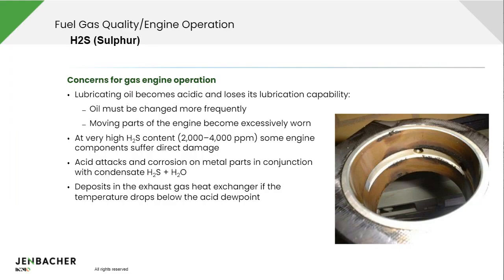The first topic is what Luis already alluded to: gas quality and gas treatment. The first thing to consider is H2S, or sulfur. Sewage gases, as well as other biological gases from digesters, typically contain quite a bit of sulfur. The issue is that when you burn these gases in an engine, the lubricating oil becomes acidic and loses its lubrication capability, meaning you have to change engine oil more frequently, and the moving parts wear out quicker due to reduced lubrication. You can measure the acidity of the oil through regular lube oil analyses, which is the best way to determine if you have a sulfur problem in the engine.